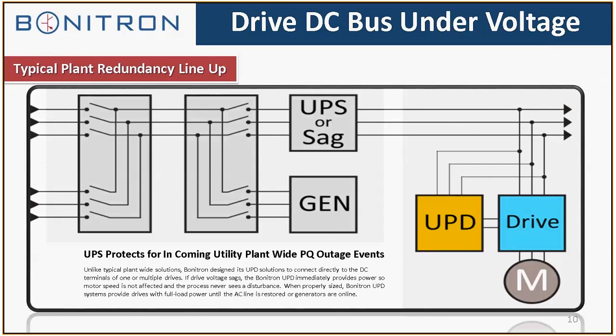Now, when we talk about redundancy and internal plant configuration, this is usually what you're going to see for a critical application. You're going to have a UPS or sag corrector at the power distribution. You're going to have a gen set that you can switch over for long-term outages. And then you'll have the Bonitron UPD right next to the drive, parallel to the drive, DC bus and the AC line connected. So this would be what we would call N+3 redundancy. There's 3 levels of redundancy here for backup protection. There's the UPS, there's a generator, and there's a process level. A lot of critical applications require this, and some of them actually go up to N+4 redundancy also, especially with data centers.